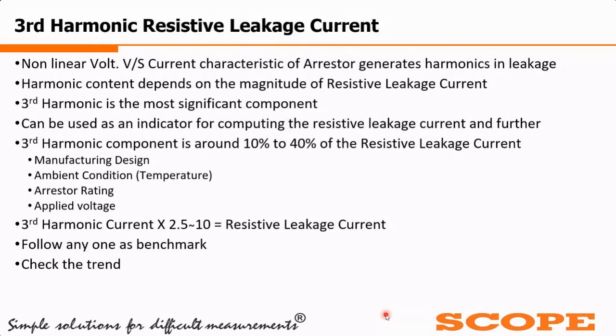So in short, if we multiply the third harmonic current that we are measuring by a factor between 2.5 and 10, because 2.5 comes if it is 40% and 10 comes as the factor if it is 10%, then I will be getting the value of the resistive leakage current. Now the most significant thing is that we can measure or take care of all these three parameters: ambient condition, arrestor rating, applied voltage. These three things we know at the time of measurement.